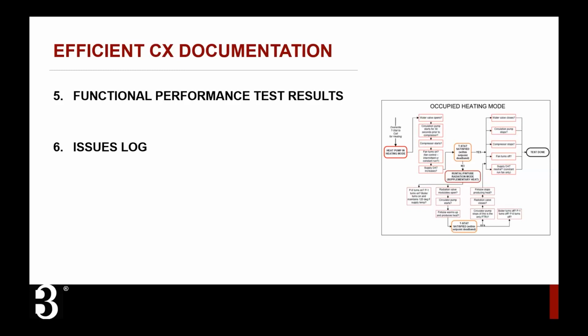From the functional performance tests, site visits, and checklists, the commissioning agent should always keep an issues log. This tracks deficiencies and outstanding items in one location, so all parties are aware of them, who's the responsible party, and when the proposed fix time is. It gives the owner a check to make sure that when they're handed the building, all deficiencies have been corrected, and it serves as a future reference for things they may need to watch. This should be developed early on, maintained, updated, and resolved before the end of the project.